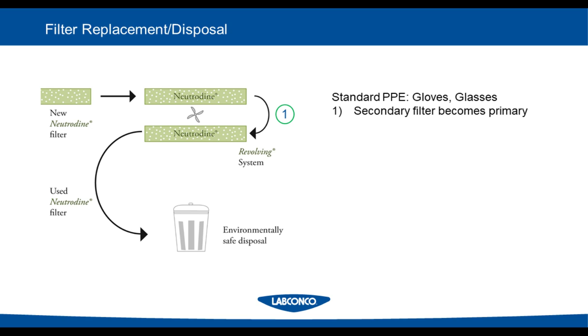There are a couple options there. Easiest and simplest is high temp incineration as hazardous waste. The good news is carbon filters have a lot of embedded energy. Activated coconut shells are the medium we use, the best on earth, with 15,000 square feet of surface area per gram. All of that surface area is adsorbed chemicals.